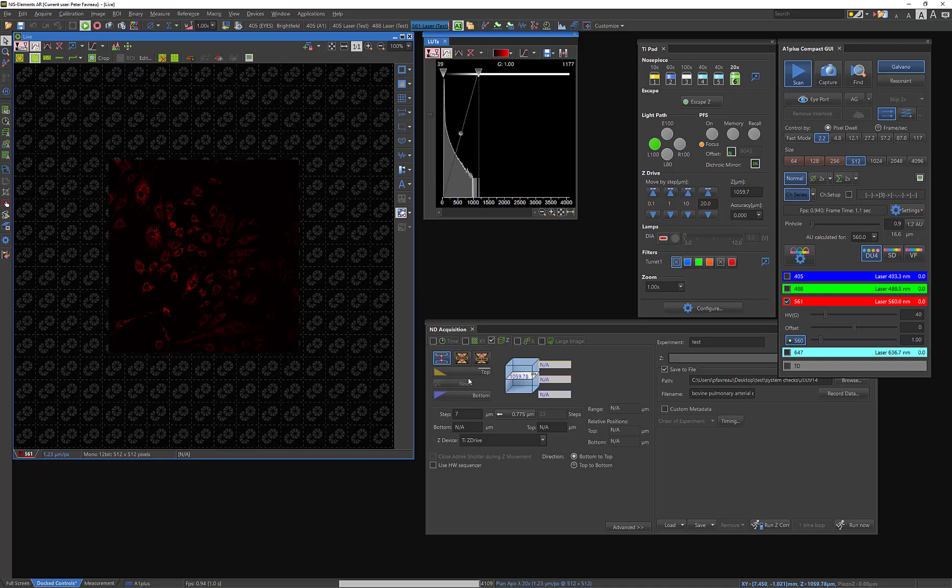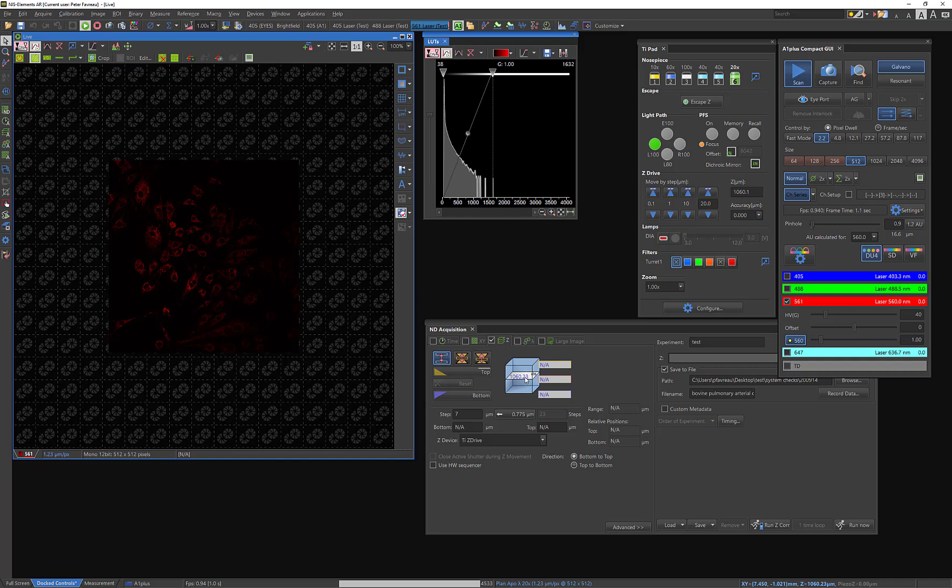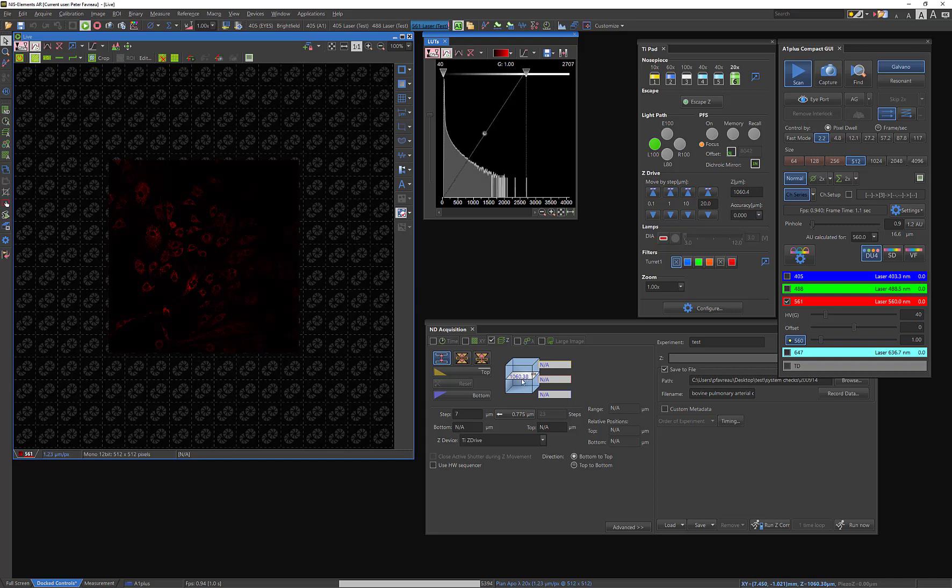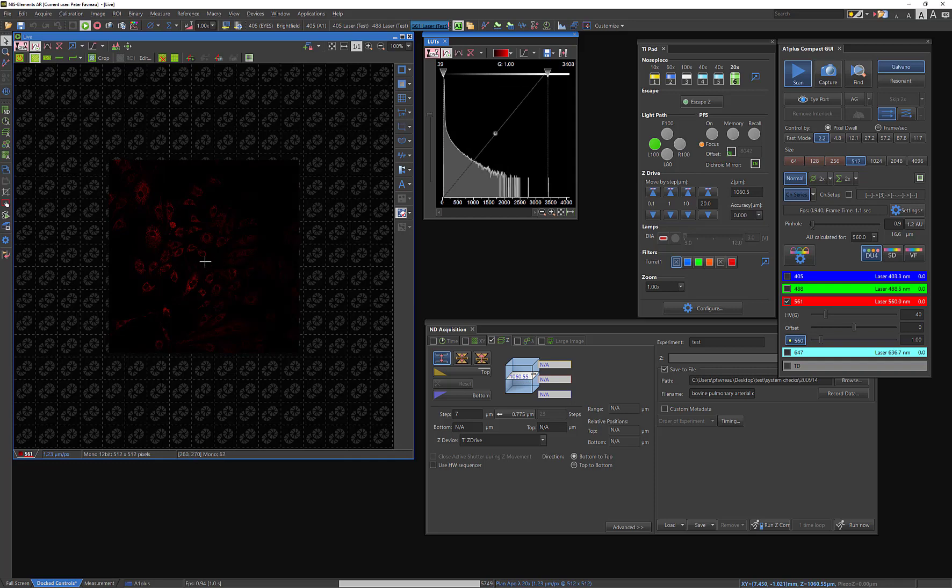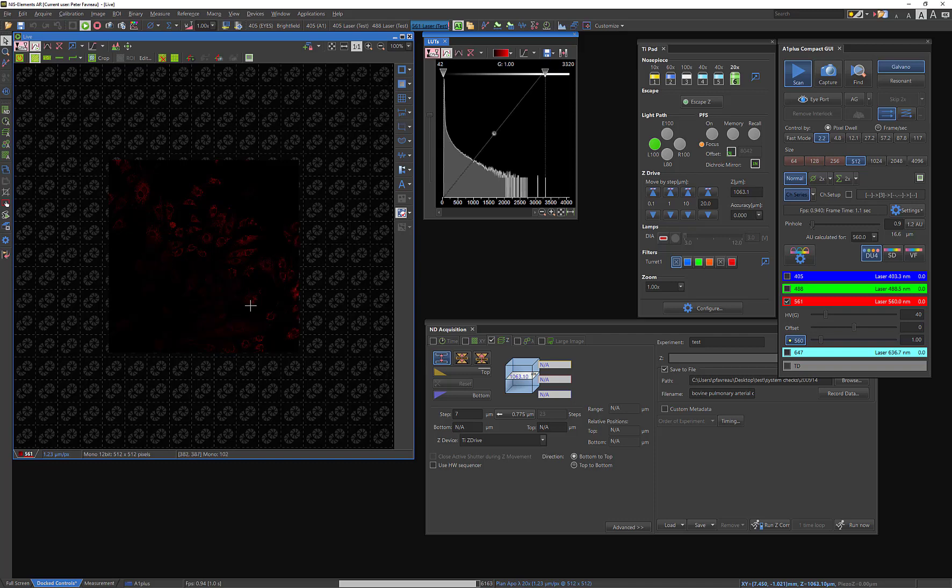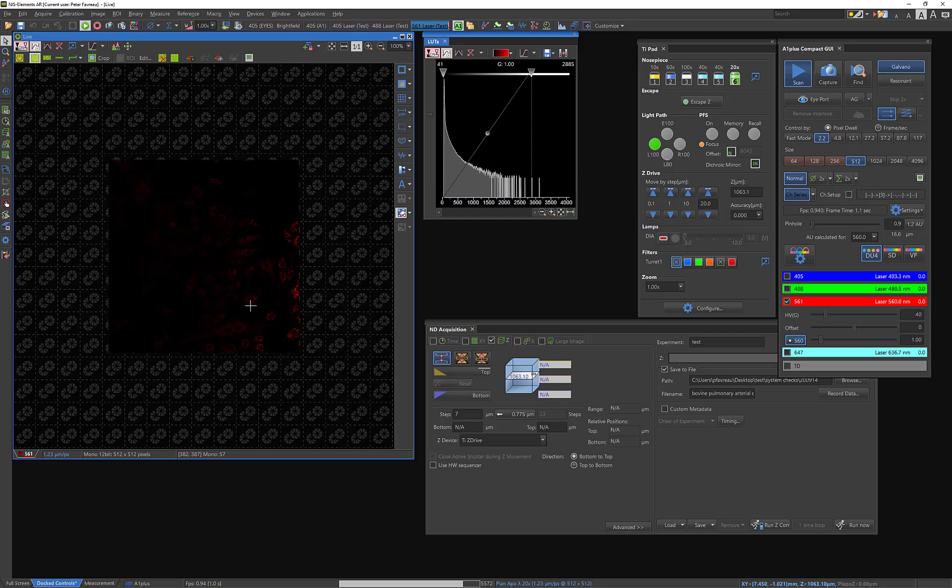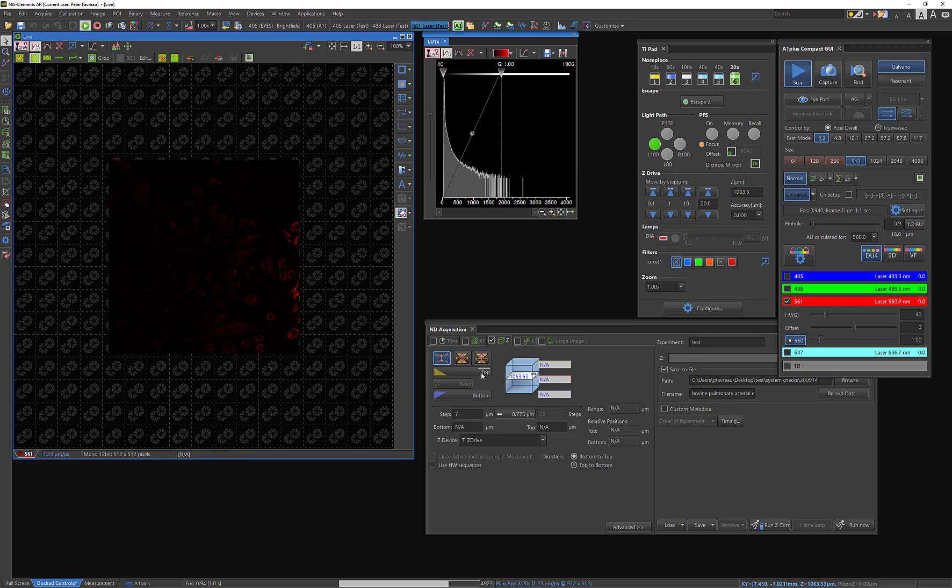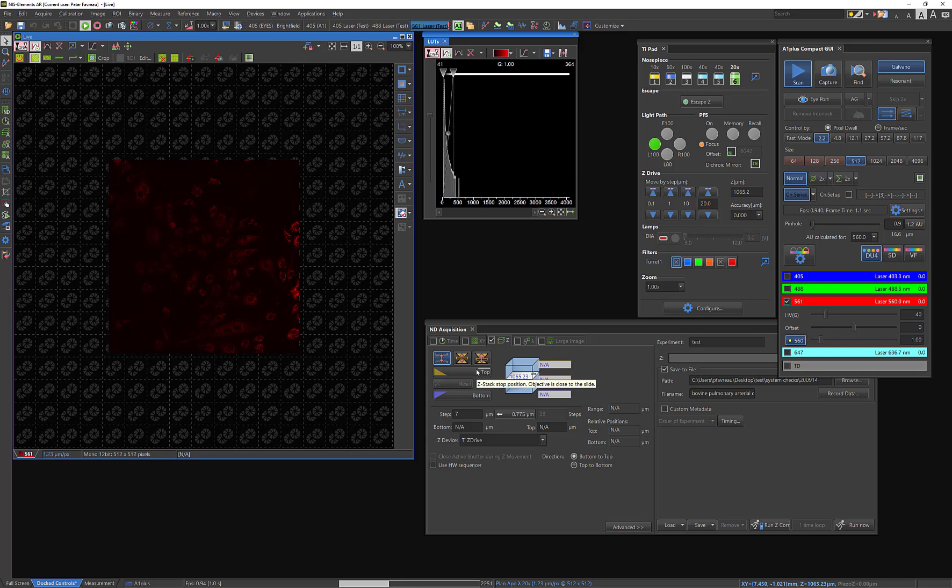And you can tell it's going to the top by the number here is going to go up, right? So right now it's going to 1060. And I'm just going to have it go. And basically what I should see here is that this should gradually go out of focus. It's going up a little bit more. And now it's pretty much out of focus completely. It's a little bit because there's some brighter areas.